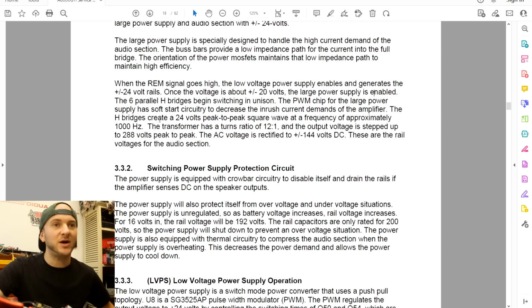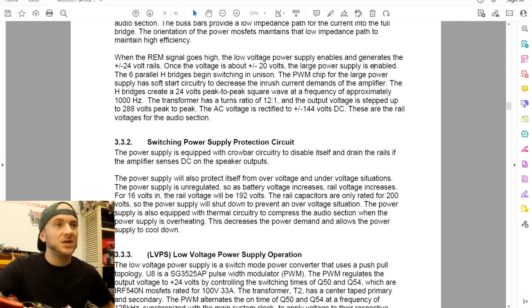The PWM chip for the large power supply has soft start circuitry to decrease the inrush current, etc. That will probably just be gradually increasing the duty cycle of the pulses leading to these FETs, ramping up slowly. It tells you the peak to peak voltage of the square wave, and the switching frequency of the transformer, which is 1000 Hertz.